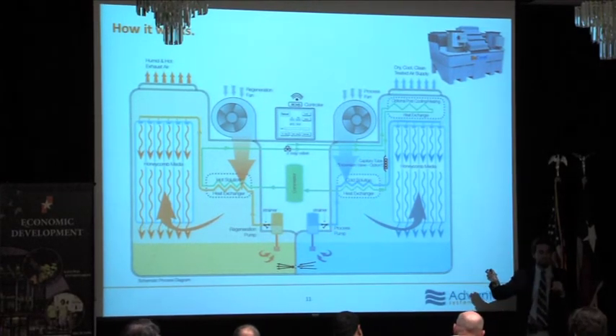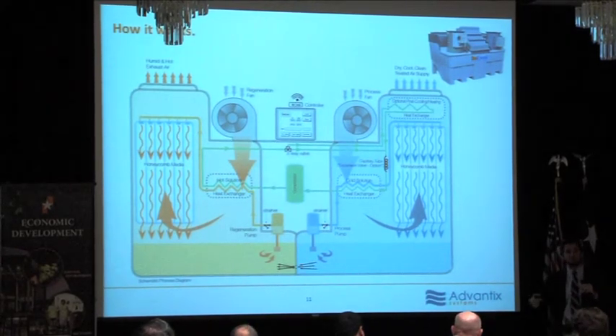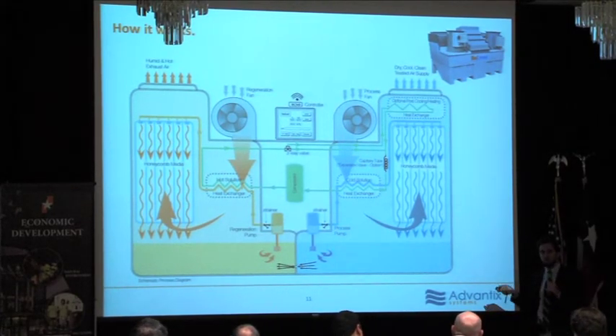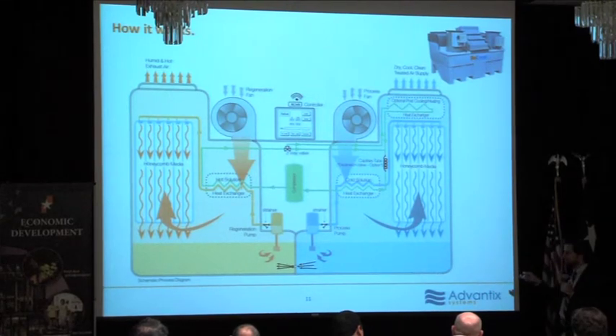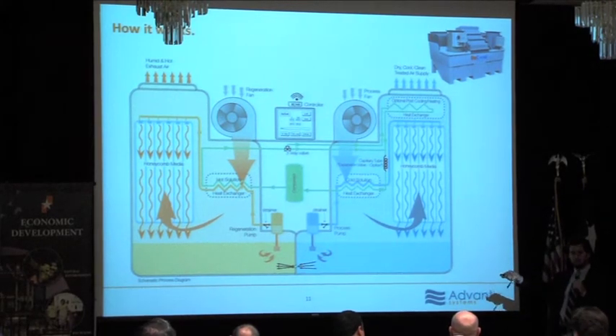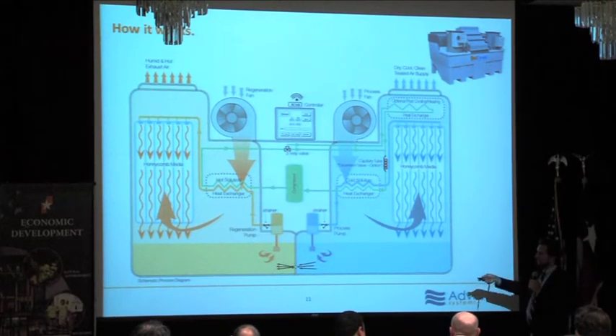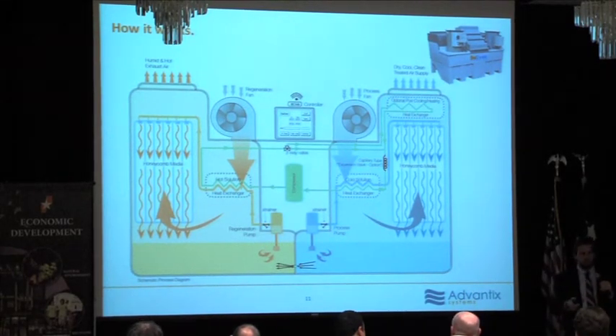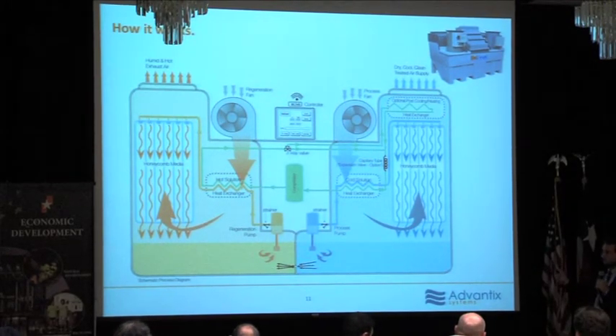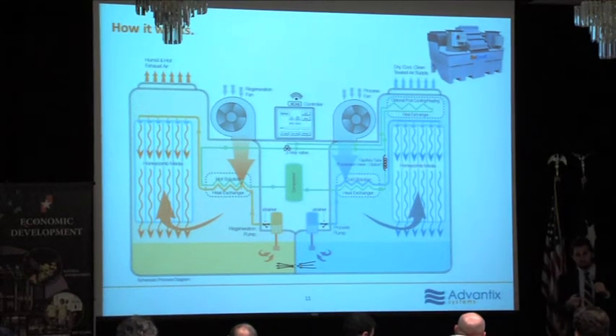If you've got a lot of heavy sediment in the air, an example in Florida is people that live near the Everglades, which start on fire and there's all this ash in the air, you need to perform a process similar to a cooling tower scrub where you just remove the media, and in this case you remove the desiccant, you pump that out into a separate container, and then you just scrub the bottom of that thing out. We haven't seen anybody that's needed to do that more frequently than every 5 years or so. That process is something where you have to take the top off the unit, so it takes about 2 or 3 hours to execute that. Good question.